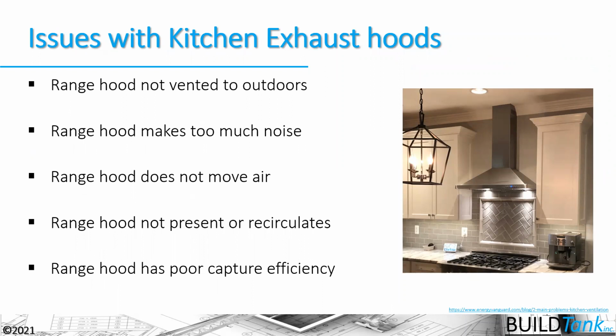Issues with exhaust ventilation include that the hood is not actually vented to the outdoors, so we're pumping those pollutants and potential moisture into building cavities if we're not venting them properly. The hoods make too much noise, so we're not actually using them. It doesn't move enough air, so we're not getting those pollutants out. The hood's not present, or it's a recirculating hood that just dumps the pollutants back into our house with maybe poor filtration on it, or the hood doesn't have the right capture efficiency.